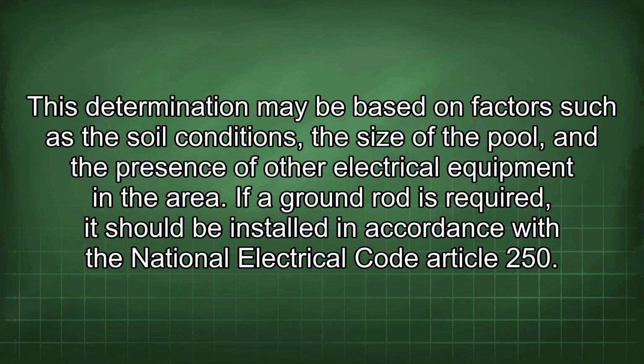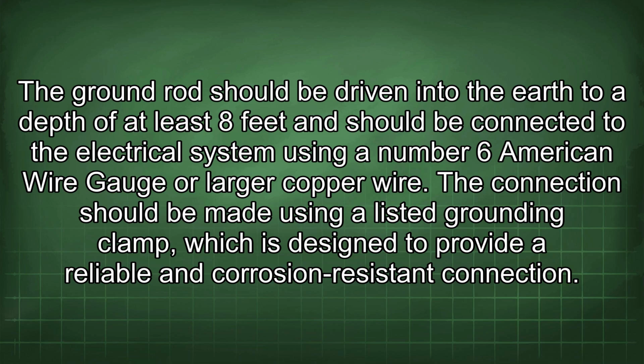This determination may be based on factors such as the soil conditions, the size of the pool, and the presence of other electrical equipment in the area. If a ground rod is required, it should be installed in accordance with the National Electrical Code Article 250. The ground rod should be driven into the earth to a depth of at least 8 feet and should be connected to the electrical system using a number 6 American wire gauge or larger copper wire. The connection should be made using a listed grounding clamp, which is designed to provide a reliable and corrosion-resistant connection.